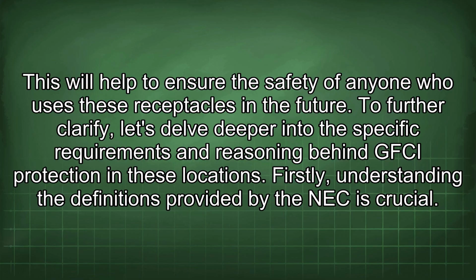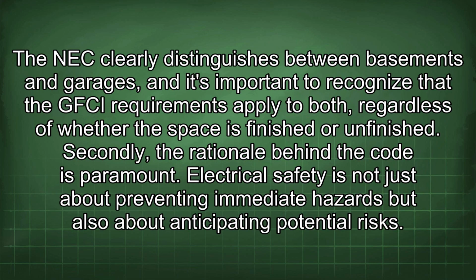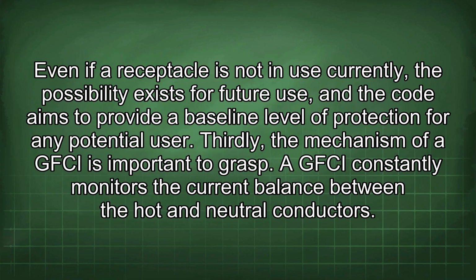Firstly, understanding the definitions provided by the NEC is crucial. The NEC clearly distinguishes between basements and garages, and it's important to recognize that the GFCI requirements apply to both, regardless of whether the space is finished or unfinished. Secondly, the rationale behind the code is paramount. Electrical safety is not just about preventing immediate hazards but also about anticipating potential risks. Even if a receptacle is not in use currently, the possibility exists for future use, and the code aims to provide a baseline level of protection for any potential user.